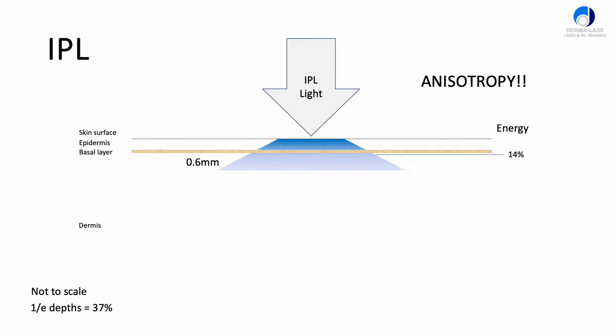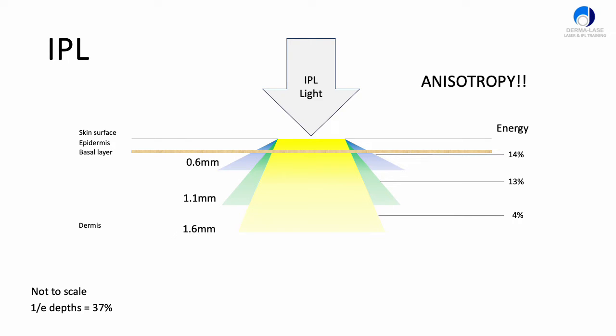The green light will spread like this — its anisotropy is not quite as bad as blue light, so it doesn't spread out quite so widely, and it will penetrate to about 1.1 millimeters depth. Green light constitutes about 13% of all the IPL energy. Yellow penetrates down to about 1.6 millimeters, but there's only about 4% of this energy in the yellow band — it's not a large bandwidth at all. The red and orange colors penetrate to about 2.6 millimeters and constitute about 17% of all the energy.